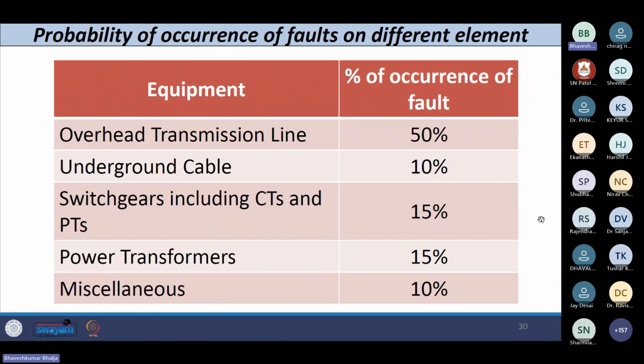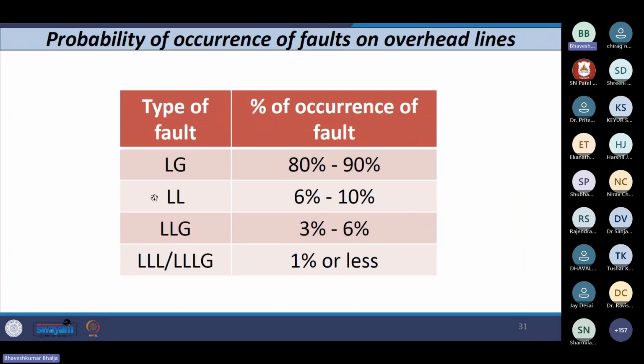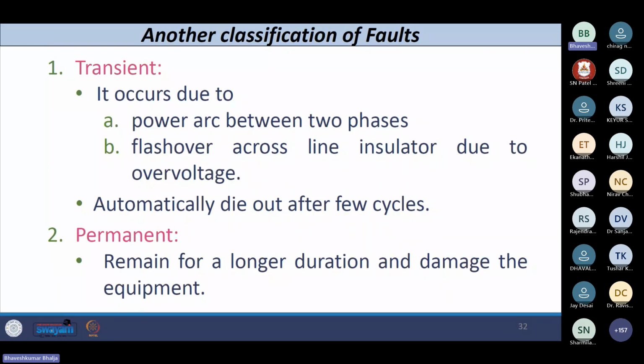If you look at the percentage of occurrence of faults, the maximum occur on the overhead line, let's say 50%. And if you consider the type of fault, then 90% of faults are line to ground faults, and that's why we are more bothered about this. Now we have established that 90% of the total faults are line to ground faults.